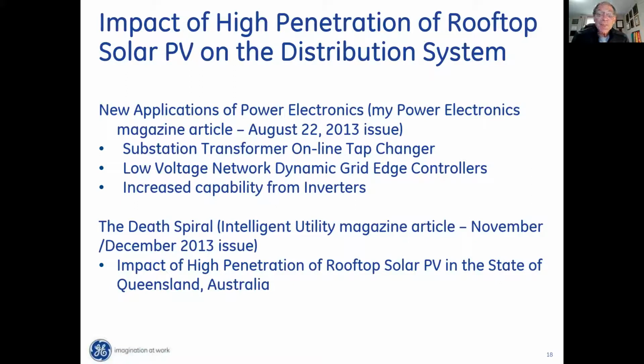So my point in writing this article was, we need power electronic based tap changers. We can't use mechanical controllers on the future grid—it's just not feasible, because there will be higher volatility of voltage and reactive power.